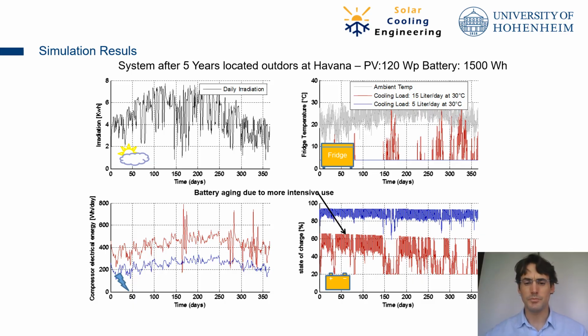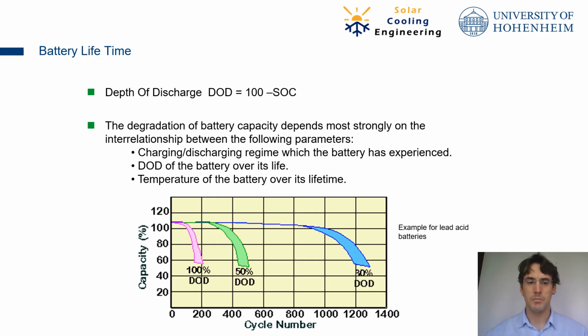So this is very interesting to see how this can affect the design. And as I mentioned before, battery lifetime depends a lot on the DOD, the depth of discharge, which tells us how much you are discharging the battery per day or per cycle. So a depth of discharge of 100% means we are discharging the battery 100% every day, going from 100 to 0.